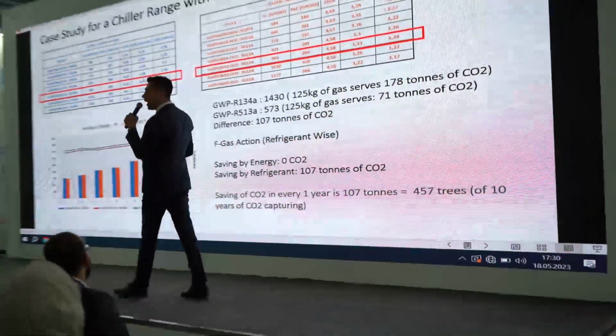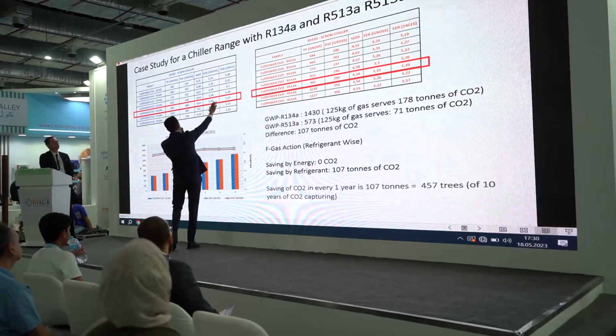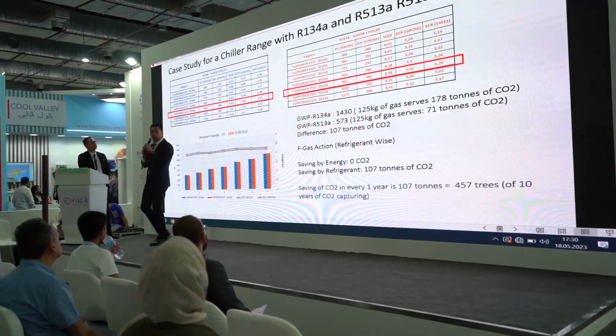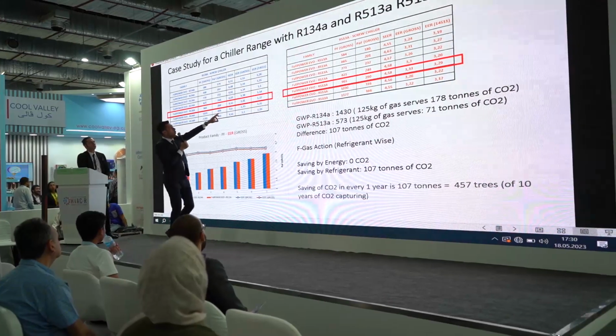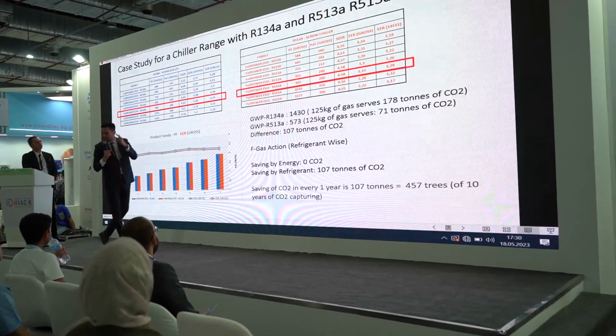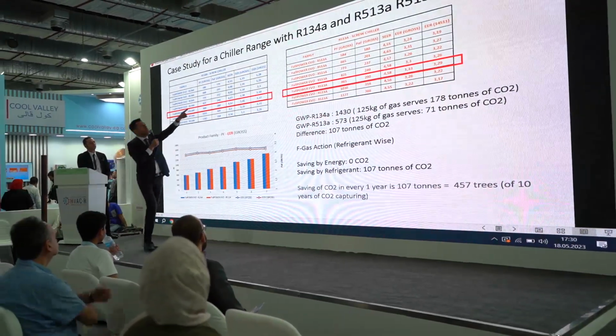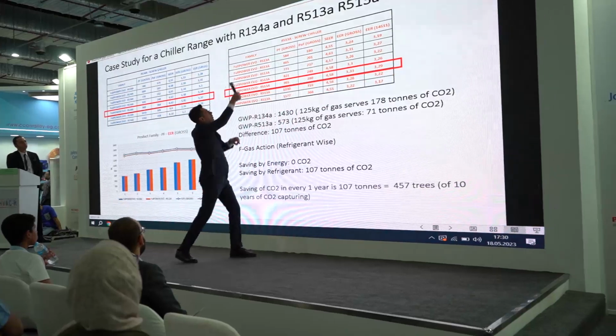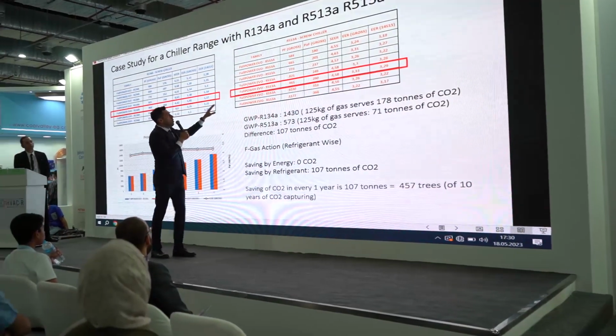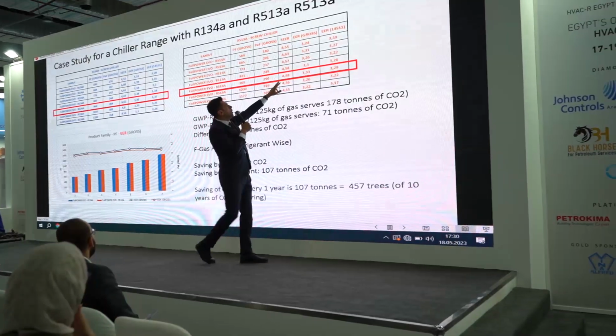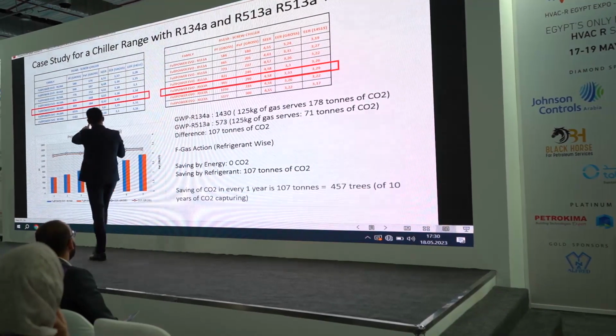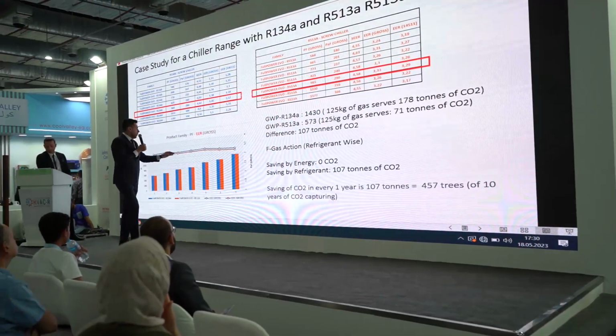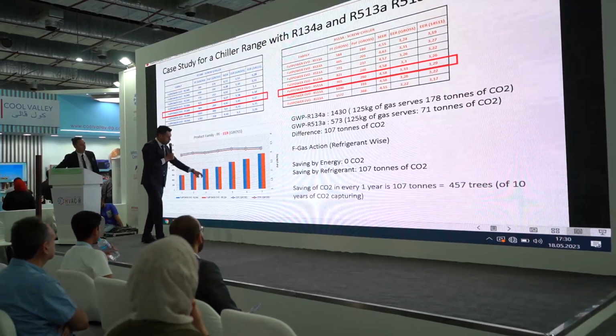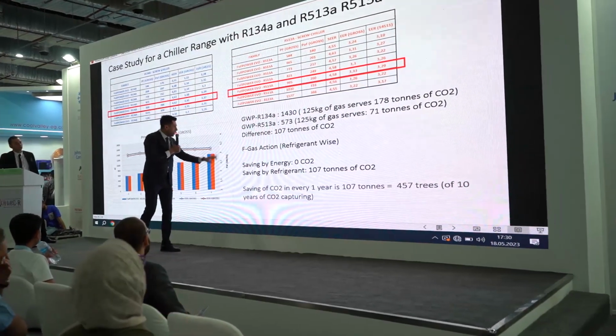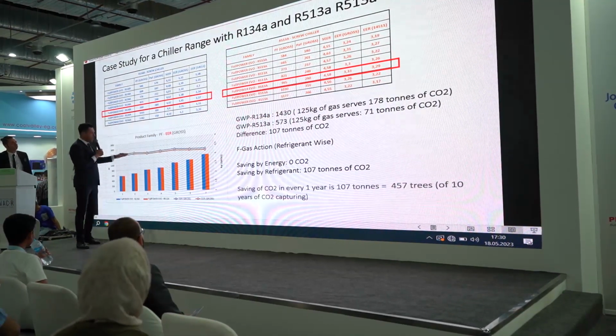You see, the first part is the normal chiller with the existing refrigerant, 134A. I put a high energy efficient one, around 1000 kilowatt. You see the seasonal energy efficiency, 4.62. I put a higher one to make a fair comparison. And same thing, I did 513A refrigerant. You see that? 513A. So same capacity almost. You see the seasonal energy efficiency, very similar, 4.62, 4.58. So this is the comparison, unit number 1, number 2, 3, 4, 5. So the EER value is almost the same, as you see from the graph, from the line, very similar.